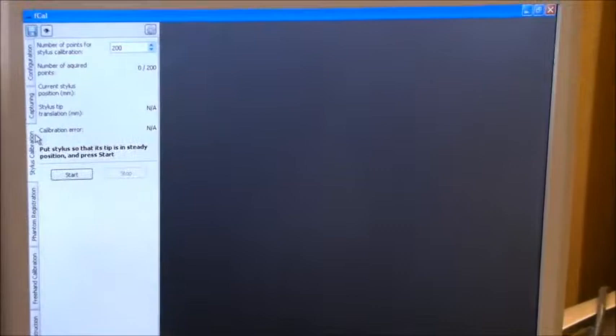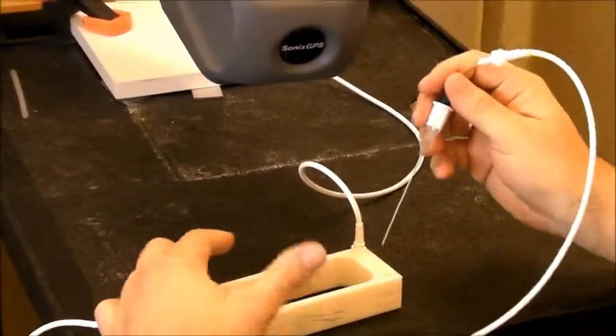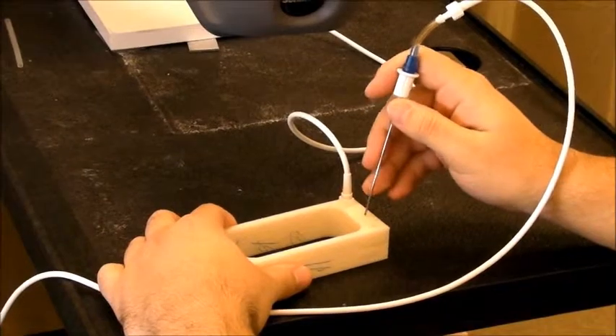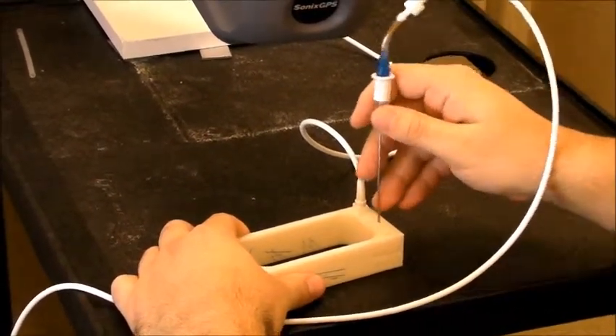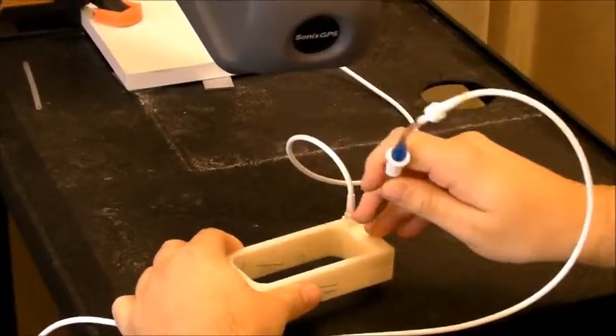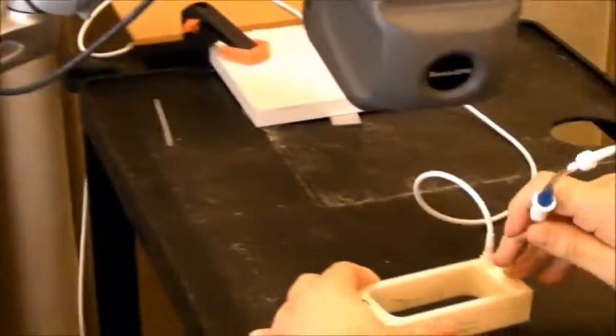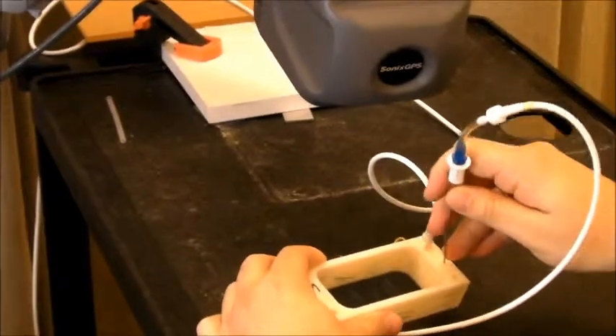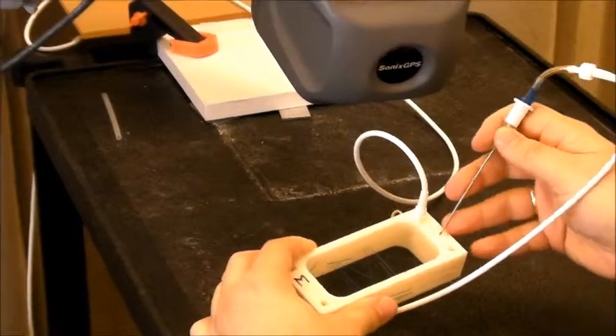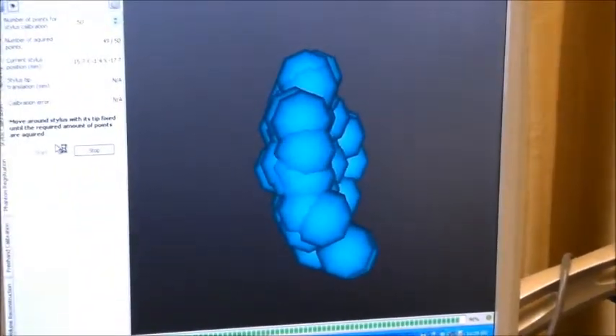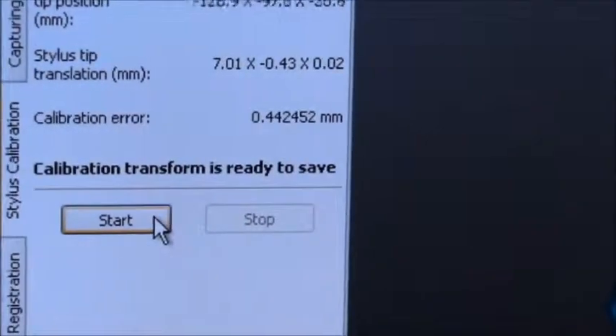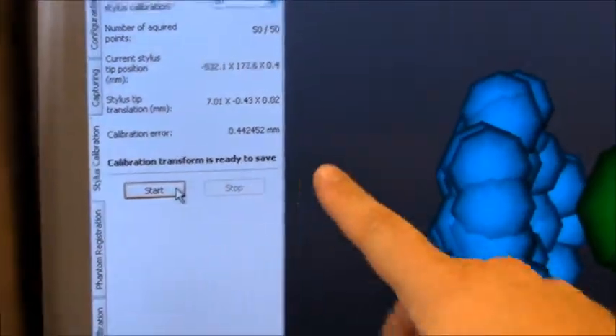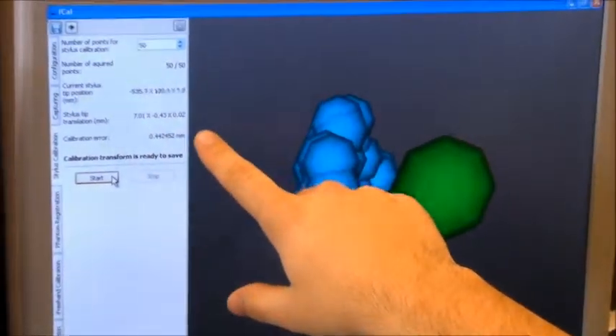The devices are connected. I go to stylus calibration. Since this is a short stylus, I just need 50 points. And I'm just going to use this foot pedal for mouse clicks. You can use your friend or buy a pedal yourself, and then you can do this alone. So you just have to make sure that the needle tip will not move with respect to the reference. Then start this pivot calibration. And as you see, points are collected on a sphere surface, and then the pivot point will be computed as the center of the sphere. Okay, it's done. My error is 0.44 millimeters, which is good, I accept that. And we have the stylus tip to stylus translation displayed.